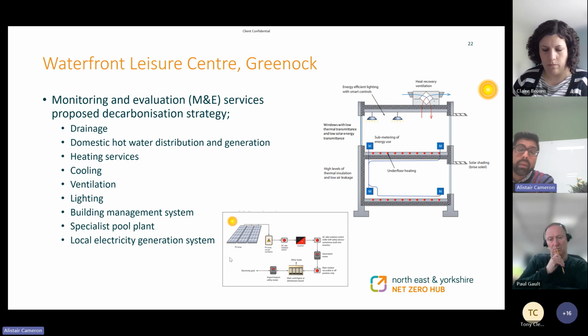And for ventilation, the building has 8 or 9 large air handling units. They're all original. They're all installed in the late 1990s. So the fan powers and the heat recovery are all of that generation in the late 1990s. So again, there's opportunities there to refurbish the air handling units, upgrade the internal components, and provide better heat recovery, more efficient fans, and essentially provide that conditioned air more efficiently.